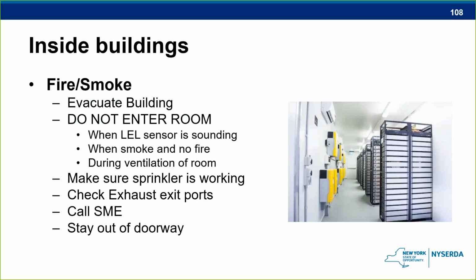We do not really want you to enter the room, especially when that LEL sensor is sounding. So maybe they have some sort of detection system that is actually measuring the hydrocarbons in there. If that thing is sounding, that means that you're getting close to the explosive limit. And you may be at that explosive limit. So are we going to exhaust this stuff? Where do we go? We have to be ready for explosions in this situation when that LEL sensor is sounding and making a noise. When there is smoke and no fire, that is our biggest concern. I'd rather see this stuff on fire than actually see the smoke because of the explosion hazard that we need to be dealing with.